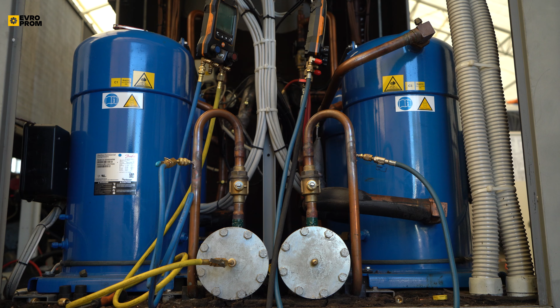For example, a Trane RTHD water-cooled chiller around 1,300 kilowatts can have 1 compressor and 1 circuit. And a Carrier 30RB around 1,000 kilowatts may have 12 Danfoss scroll compressors and 3 circuits.